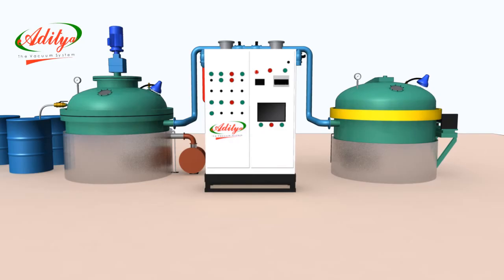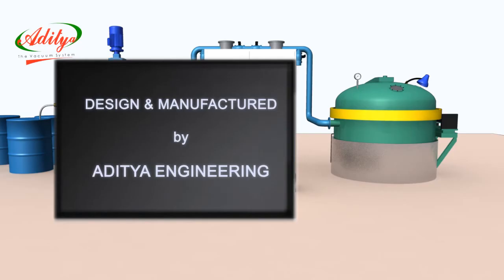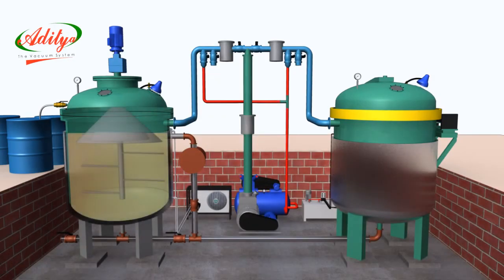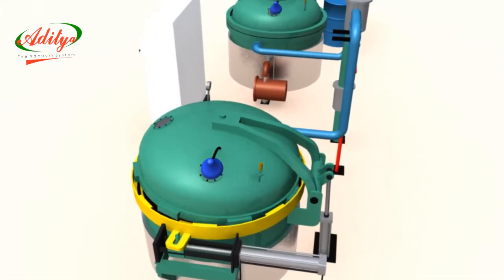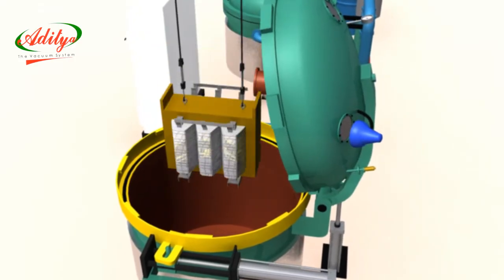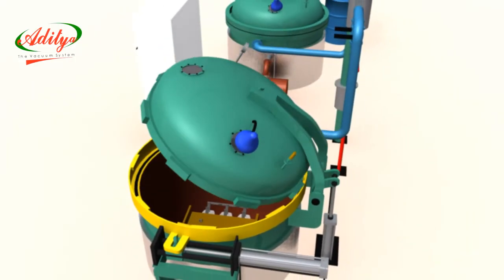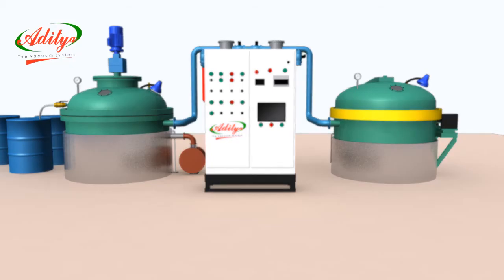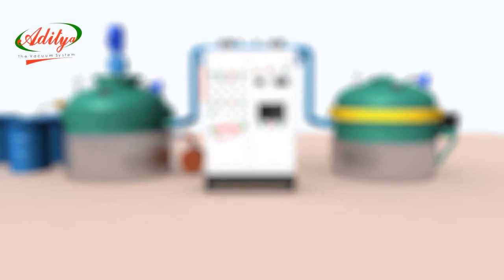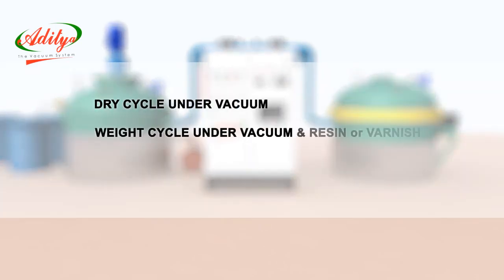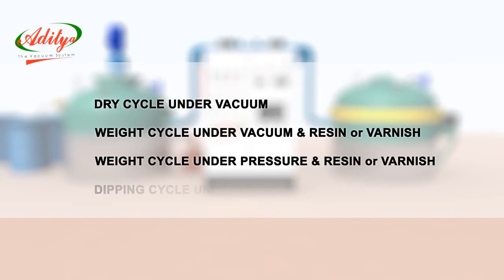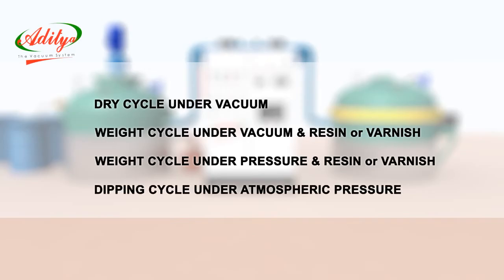The impregnating process starts with welcome screen display, designed and manufactured by Aditya Engineering. This indicates the plant is ready for operation. Vacuum pressure impregnation cycle. The auto cycle is started by pressing auto cycle start. The cycle is divided into following steps. Dry cycle under vacuum, wait cycle under vacuum and resin or varnish, wait cycle under pressure and resin or varnish, dipping cycle under atmospheric pressure.